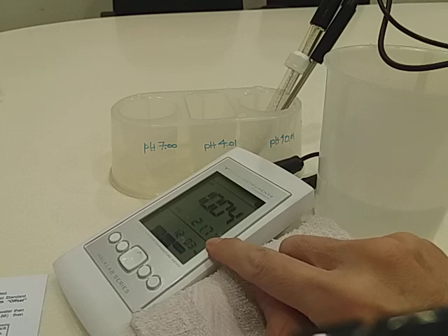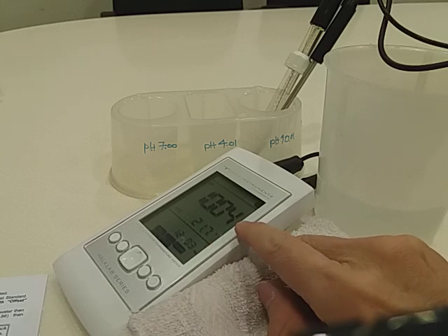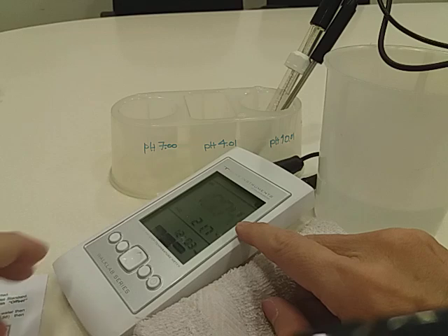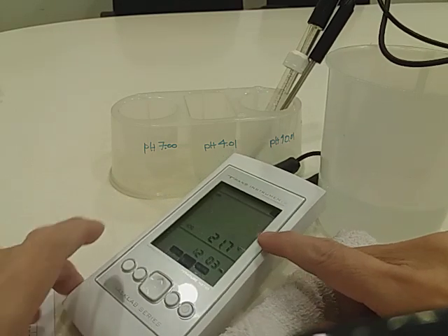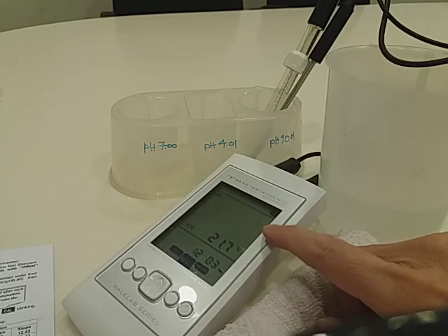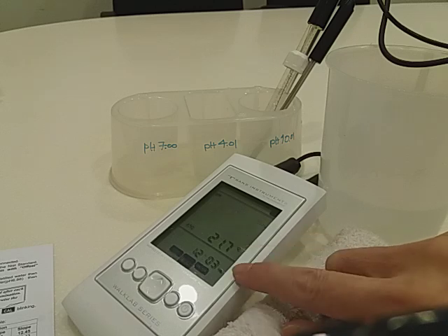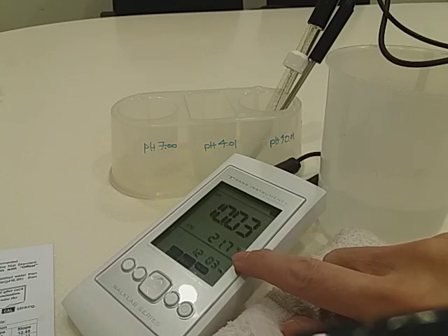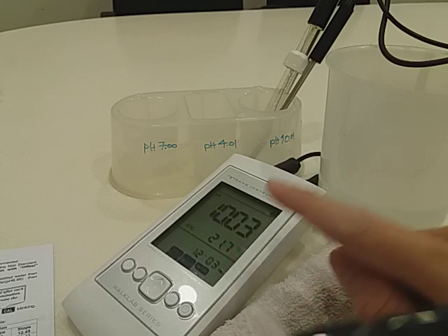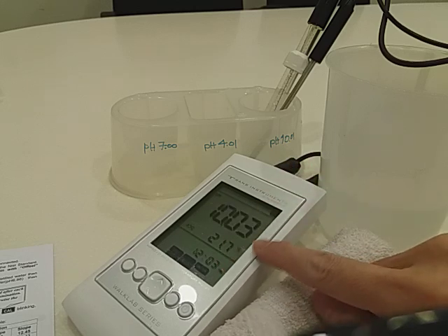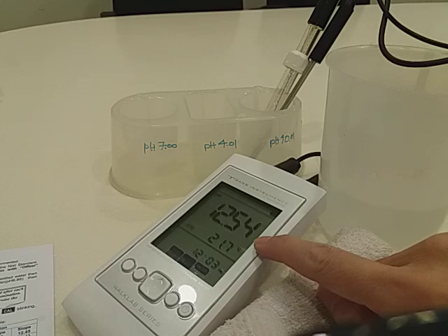And now you can see that the displayed reading at 21.7 is 10.04. So do remember that displayed reading will go according to the temperature. And sometimes it is in between, so it will give you slightly different reading. Once it's stabilized, you will hear a beep. Again, it will ask you for the rest of the buffer solution.